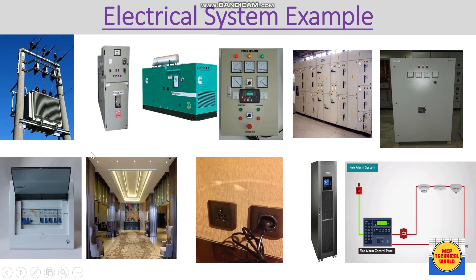Now I'm going to discuss the power distribution system in the building. Initially, we take power from the city line at 11 kV via HT cable, which is connected to the VCB panel — the high tension panel. Its output is connected to the primary side of a transformer, which steps down to 440 volts and is fed to the ATS panel. Due to interruptions in the city line, we install a DG — emergency power. This is a 500 kVA DG, and its power is also fed to the ATS panel.